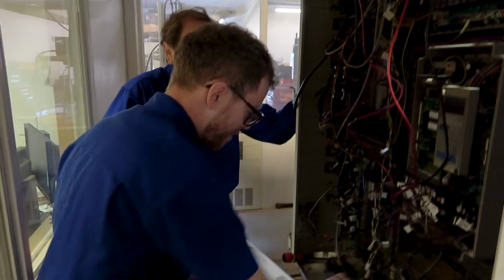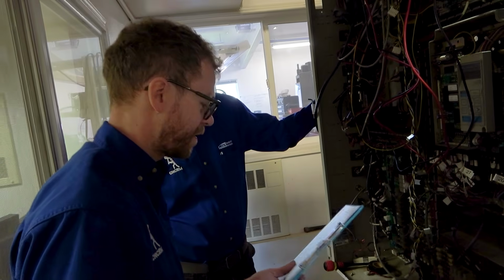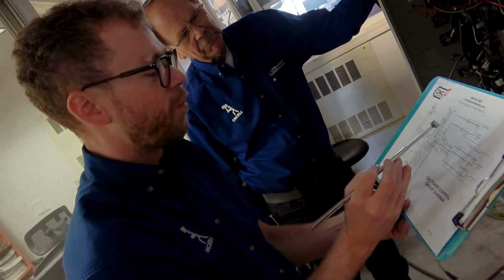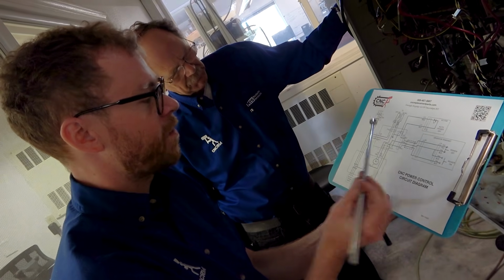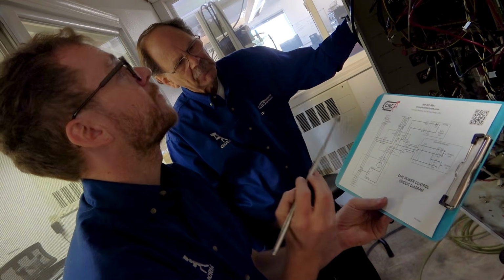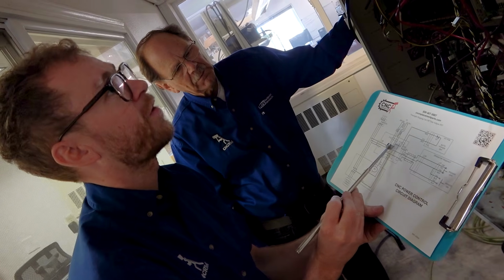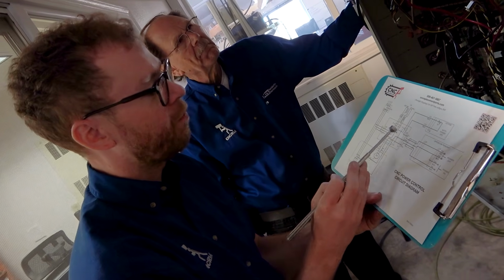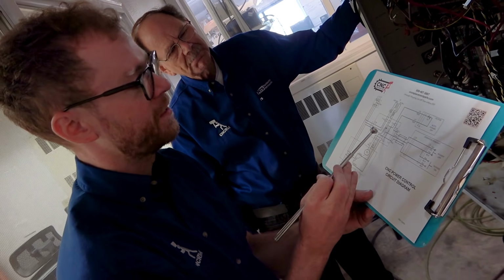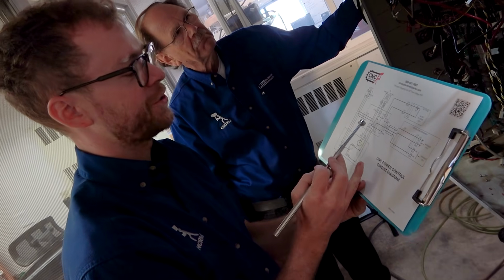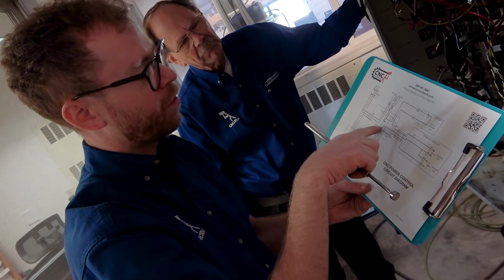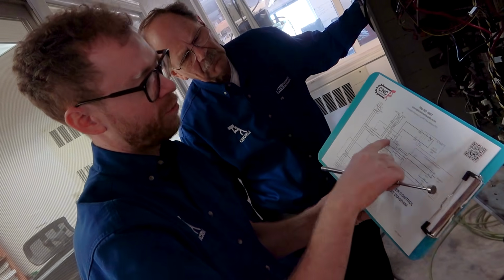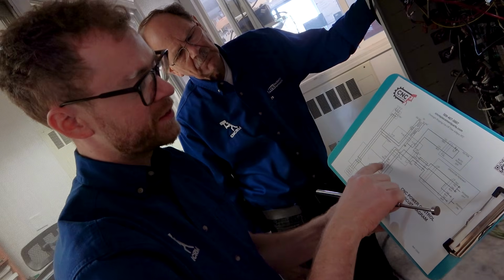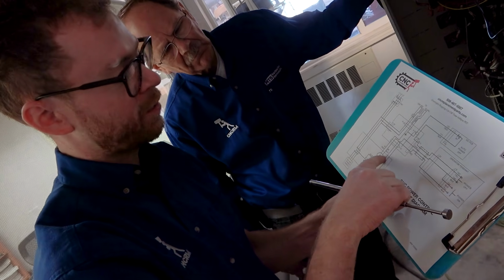Let's talk about troubleshooting this a little further, and chime in if I'm saying something wrong. We can follow this circuit. If I'm measuring 24 volts and this is tied to ground, I should be able to pull one of my leads out and touch the chassis and leave the other one there, and I still should have 24 volts. Then I can work my way down the circuit with reference to here and say, is there voltage on this side of the coil? Is there voltage on this side of the coil?